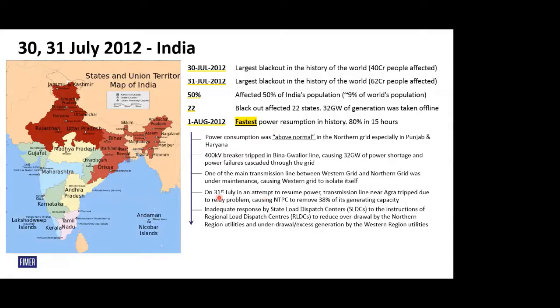On 31st July, they again attempted to charge the transformers and everything with the power available from the nearby NTPC plants. One more line in Agra, they say it was a relay problem, malfunctioned and tripped. Again, NTPC had to stop 38% of its generating capacity, causing further blackouts, and 22 states were affected, and it took 15 hours to resume the power.